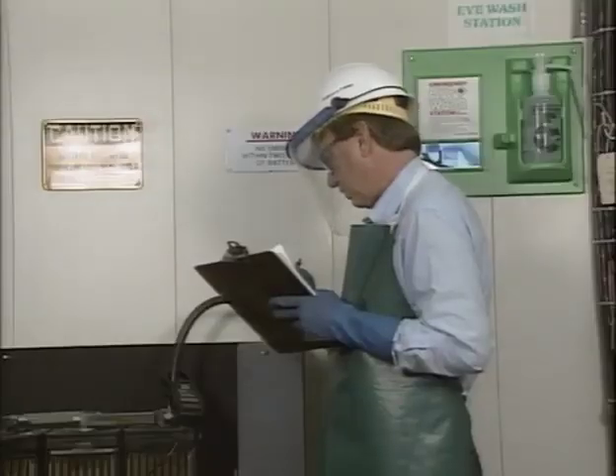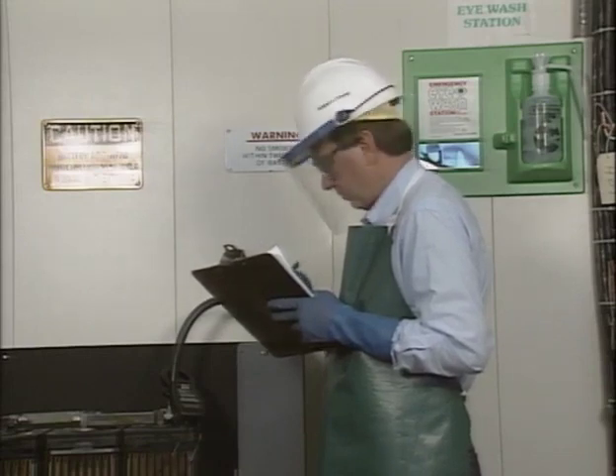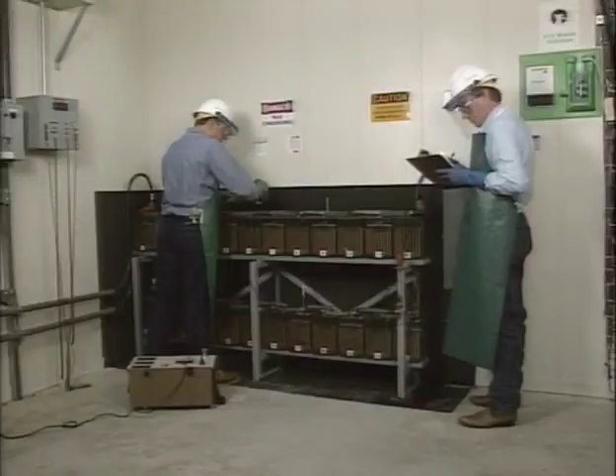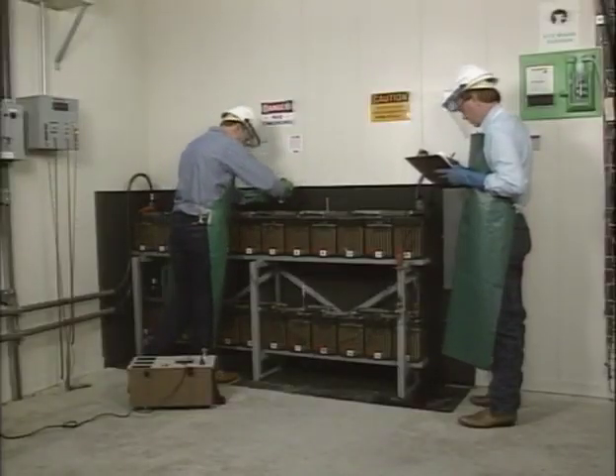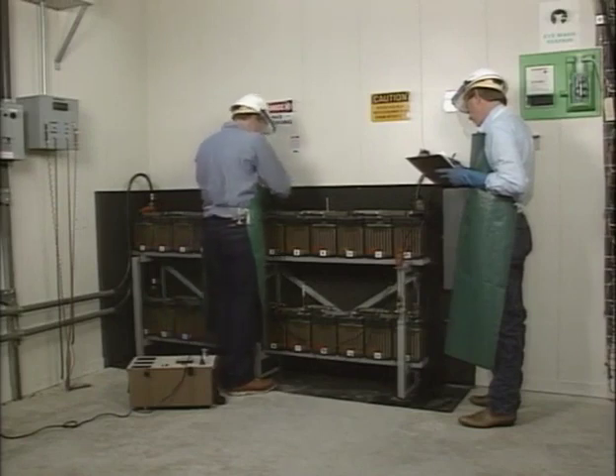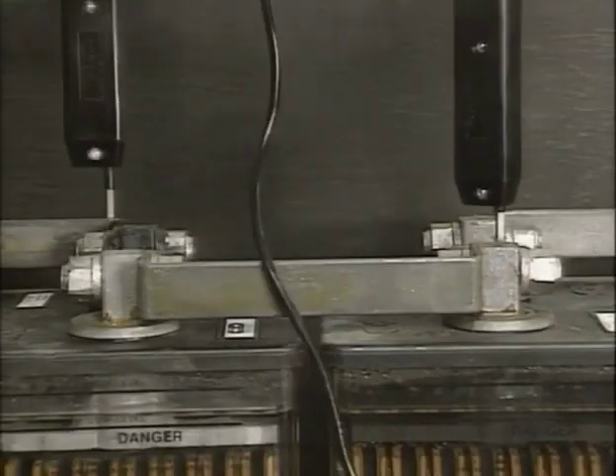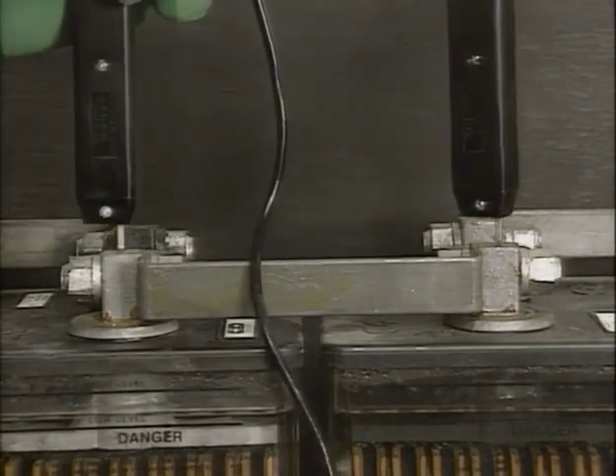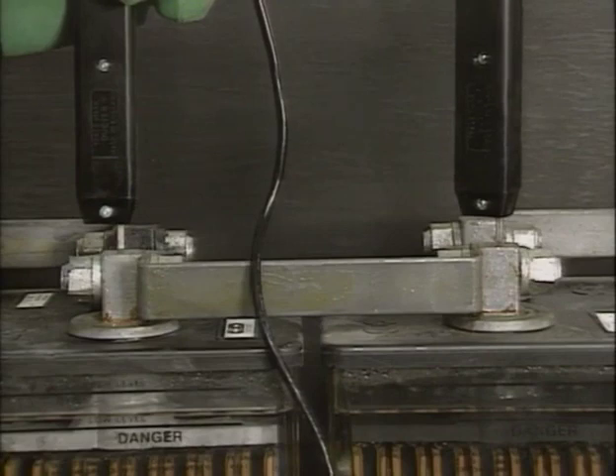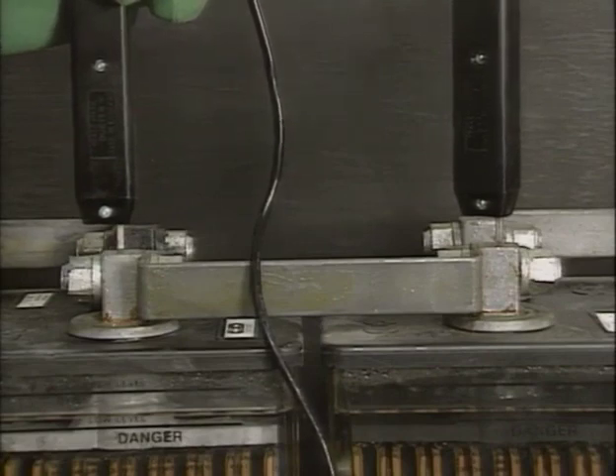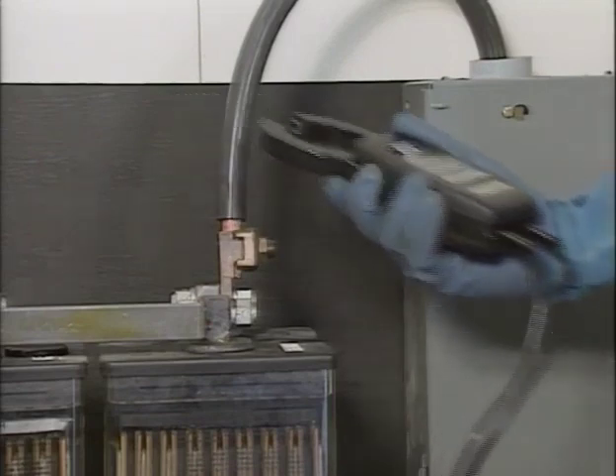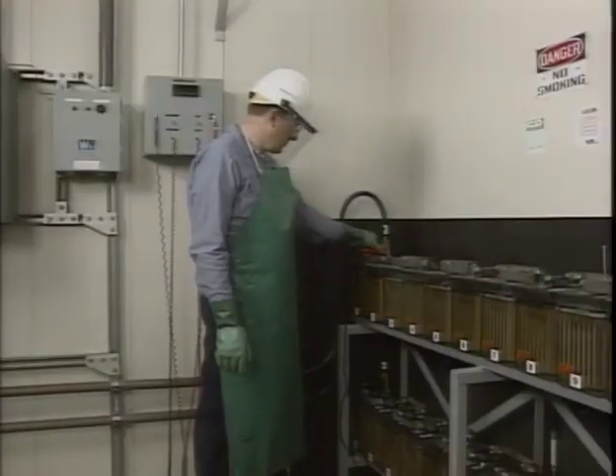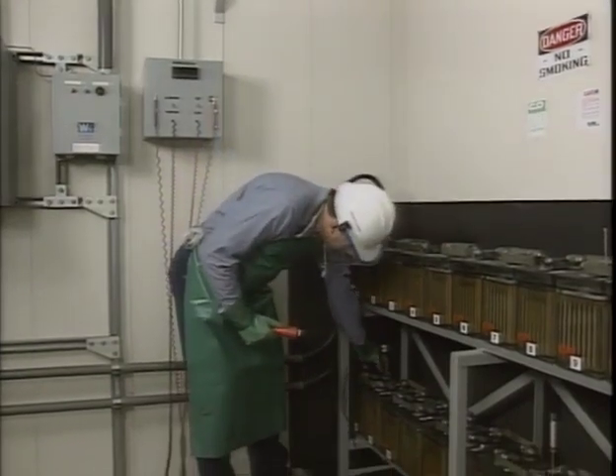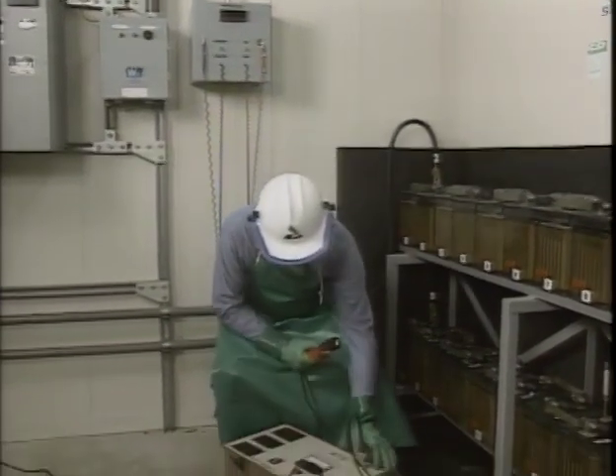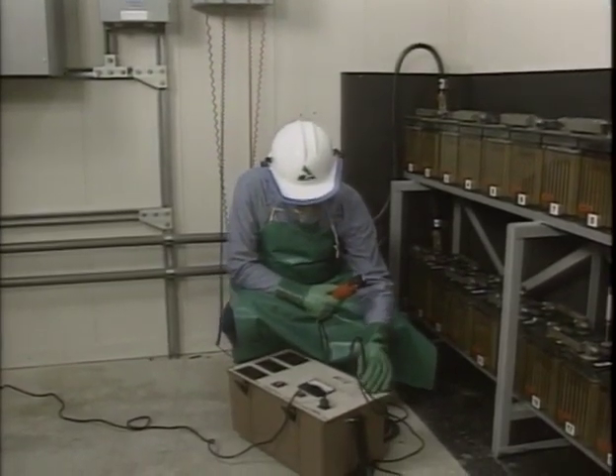The impedance is recorded on the battery impedance data form provided with the test equipment or on your company's specific test form. The impedance of each cell in the battery is checked in the same manner by simply moving the voltage probes from the terminals of one cell to another. In addition to checking cell impedance, the impedance of intercell connections can also be checked by placing the voltage probes across the terminals of adjacent cells. After the impedance tests are completed, the receiver is removed from the battery and the transmitter is turned off. Then the source leads can be removed from the battery. To avoid the possibility of arcing, the source leads should be removed only after the transmitter has been turned off.